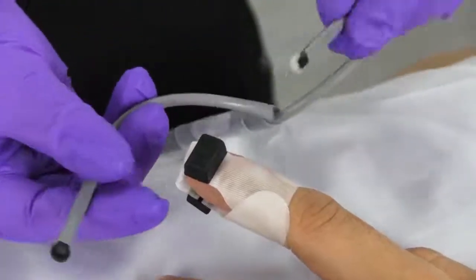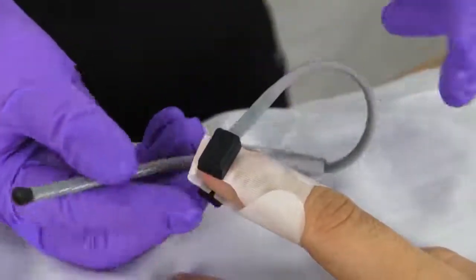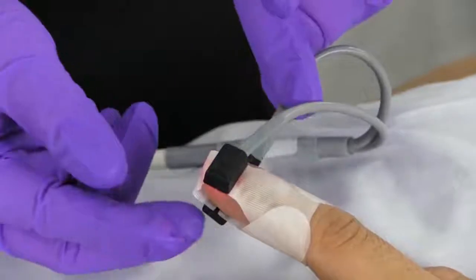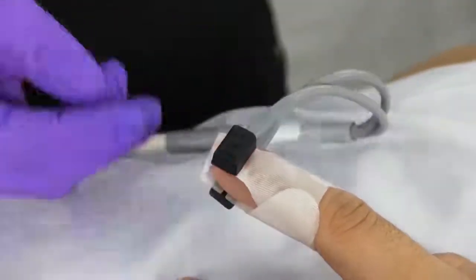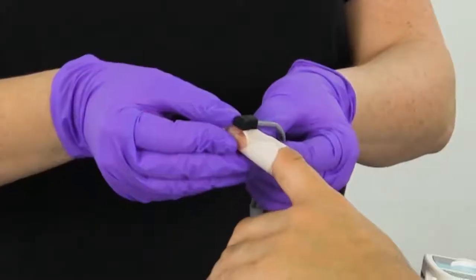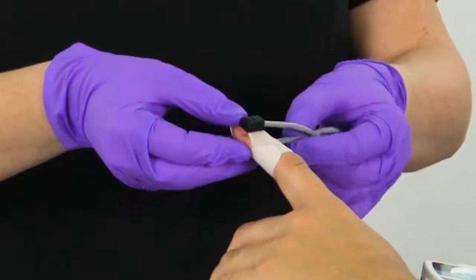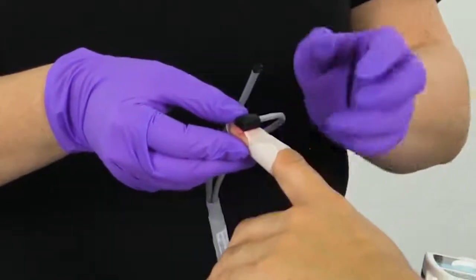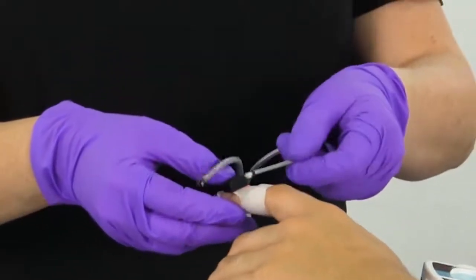When changing out the grips, be careful not to pull from the fiber optics. The fiber optics can be fragile and over time can present problems with accuracy if they are damaged. Be sure to remove the grips by pulling from the same location as attaching the grips. Pull straight out and dispose of used grips accordingly.